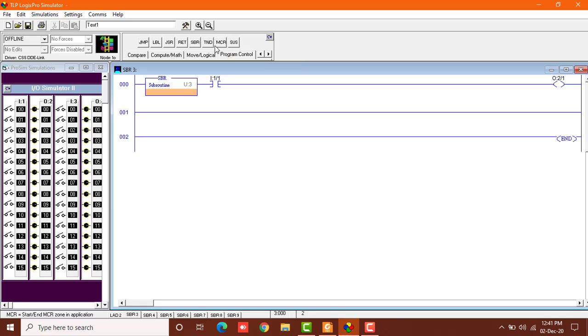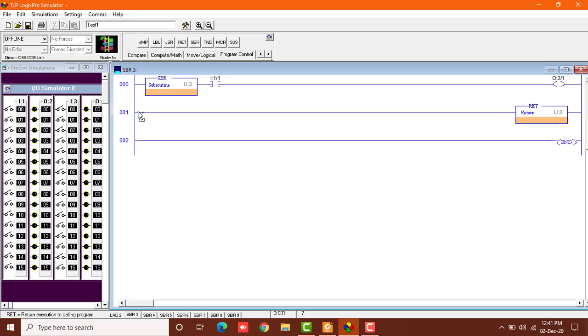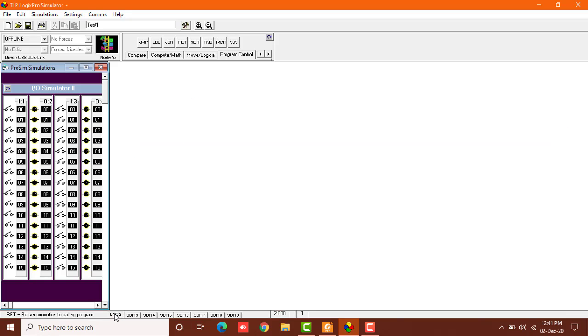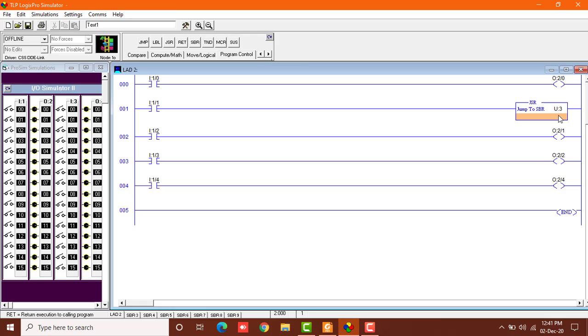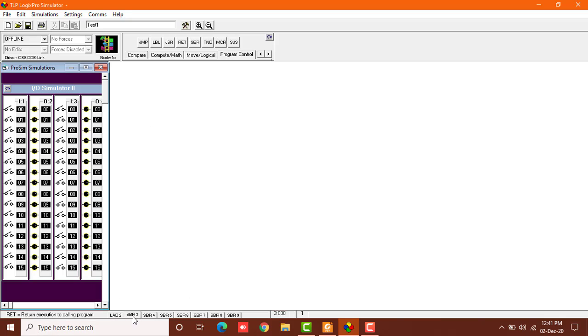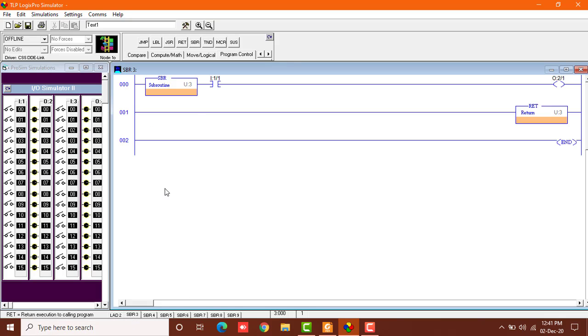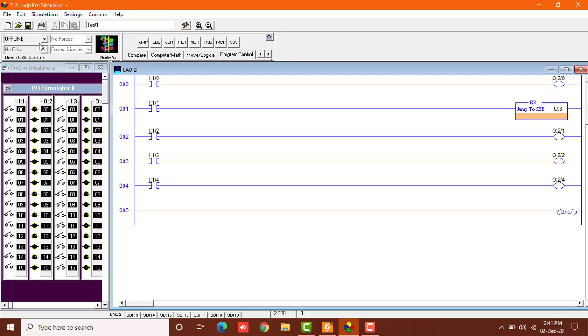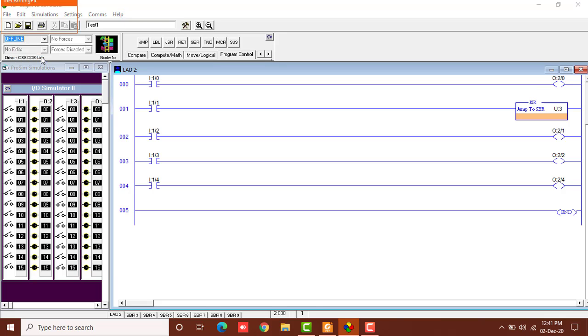So we'll pick up this subroutine end, which is a return button, and place it over here. You can see this subroutine has the same number U colon 3 which was in the ladder program of our main program. This says jump to subroutine 3 U colon 3, and this subroutine also has the label subroutine U colon 3 and the return U colon 3. Now we'll download this program to PLC and see what happens.